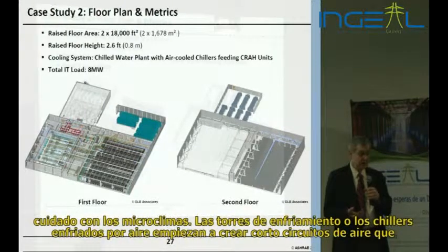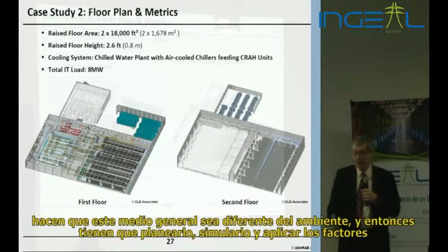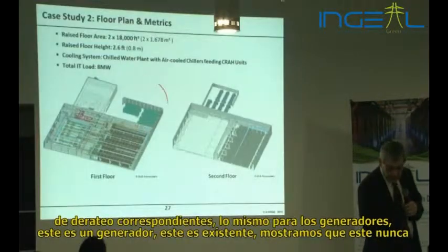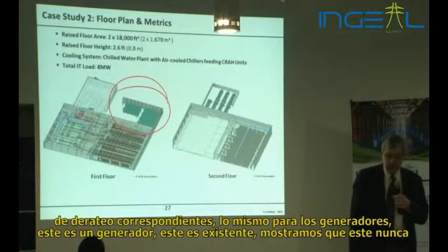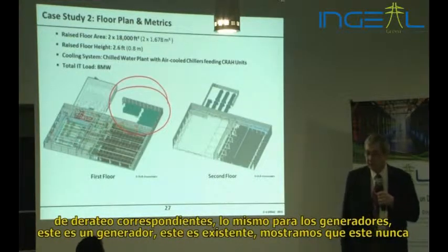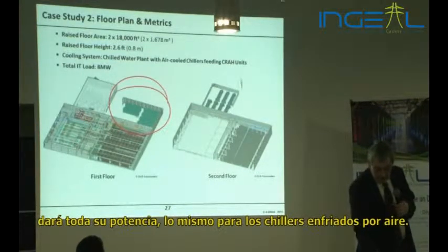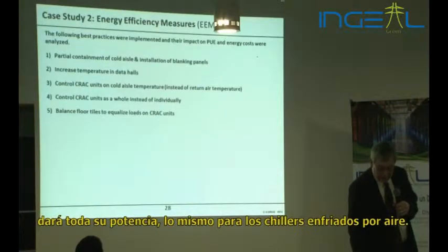about microclimate. With cooling towers or air-cooled chillers, they start to create short-circuiting and an overall environment that's different than the ambient. Therefore you have to plan for that, simulate it, and derate accordingly. Same thing with the generators - this is a generator yard that was existing, and we proved that was not going to ever fit the need. And here are the air-cooled chillers, same sort of thing.